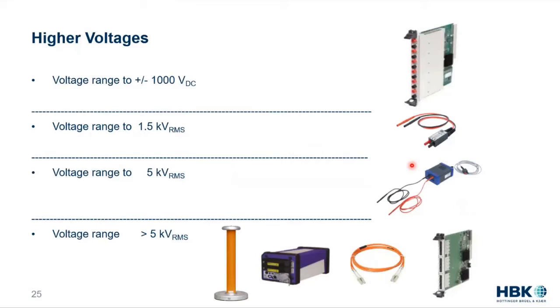So depending on the voltage, HBK has a wide variety of solutions, and I'll just go through those quickly. Our standard card, so that measurement card where we do 2 megasamples per second per channel, and we have the real-time formulas, is good up to plus or minus 1 kilovolt DC. So we can bring in 1 kV directly to that card. Cool, right out the box.